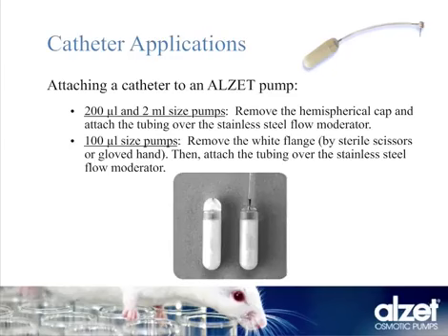Like I mentioned earlier, you can use a catheter with the pump for targeted delivery of your drug. But the question is, how exactly do you attach a catheter to the pump? Well, how you do this will depend on which pump model you have. For example, for 200 microliter size pumps or 2 ml size pumps, all you need to do is remove the cap from the tip of the flow moderator. Doing so will expose a small piece of the stainless steel flow moderator, enabling you to connect a catheter to it.